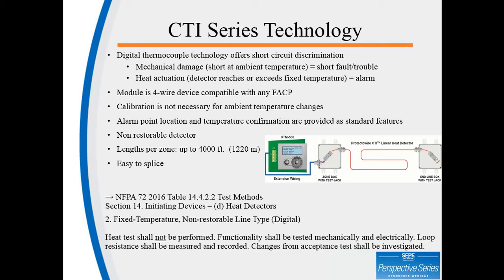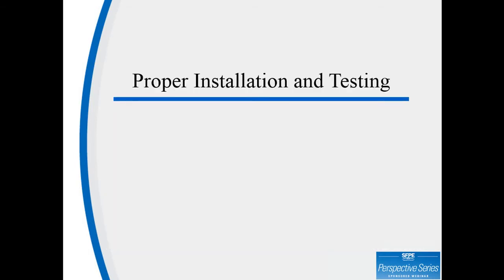As far as test methods and inspection, we still use the same chart, NFPA 72, 2016, Table 14.4.2.2. Heat tests shall not be performed. Functionality shall be tested mechanically and electrically. Loop resistance shall be measured and recorded. Changes from acceptance test shall be investigated. Proper installation and testing.